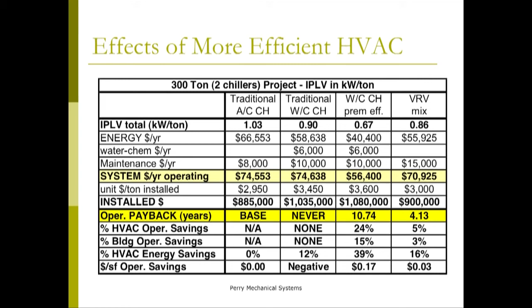If you look at the traditional air-cooled chillers as the baseline, then there's some newer air-cooled machines out there whose efficiencies, compared to a traditional water-cooled machine, make your overall operational costs very close. Actually, they're more efficient because your water treatment is so high on a water-cooled machine. Now, again, the drawback is the longevity of the machine versus the water-cooled. But you're looking at a 2-year payback on these extremely high-efficiency air-cooled machines. Now, the downside is they don't start making these things until you get up to about 200 tons.